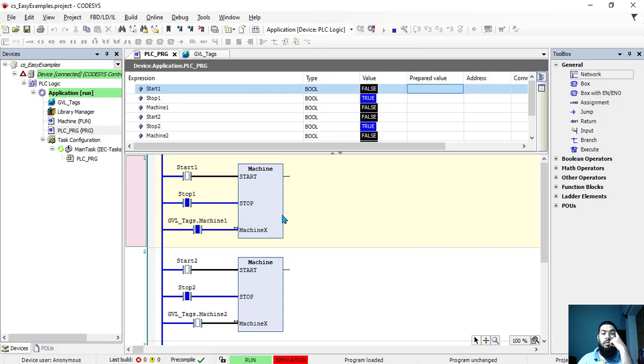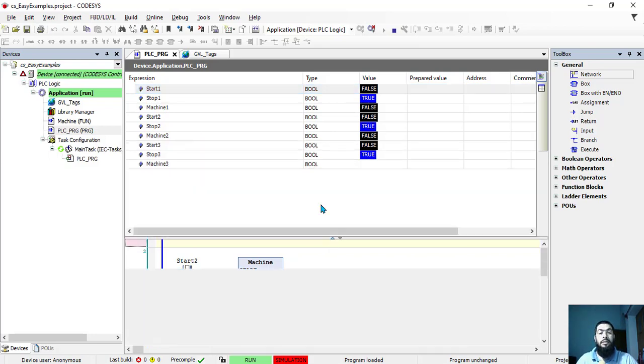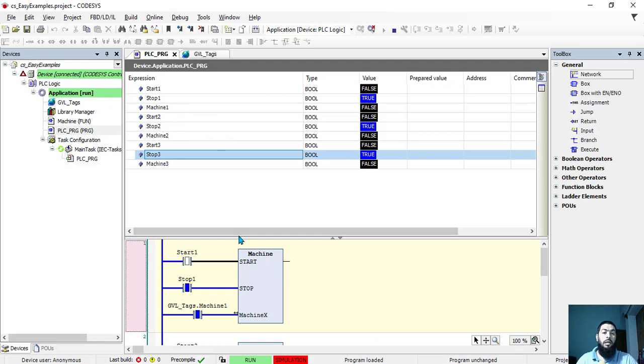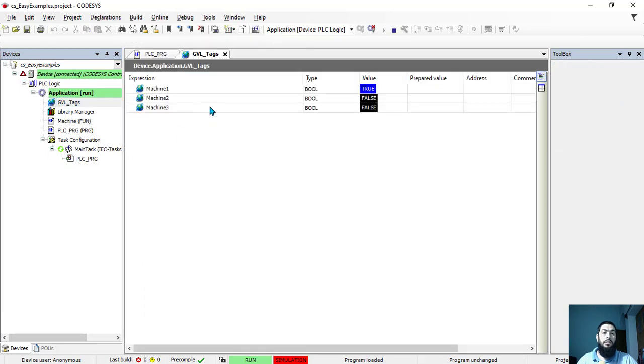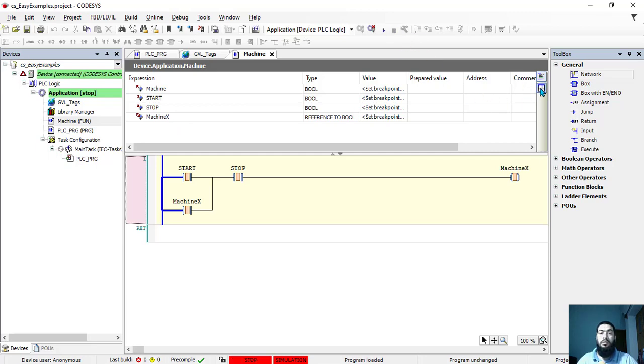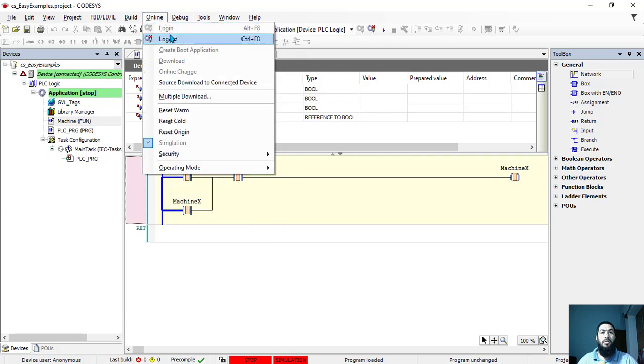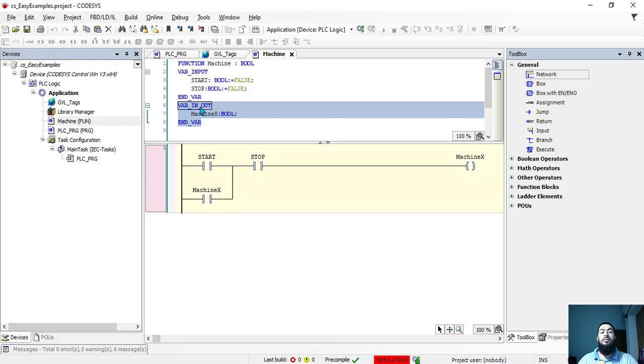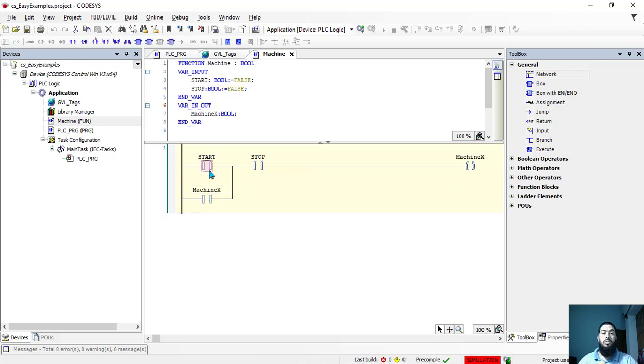So we have covered a little bit of troubleshooting and debugging of the code. What mistake did we make first? We thought the problem was because of the local tag, and then we created a global tag here, three tags, and then we found it's not the tag, but instead the problem is within the input output declaration. We declared something that is in out as output only. So this is where the problem was. When we use an output coil as input like this, these are the input instructions. So when we use such an output for the input instruction, we have to declare them as in out.